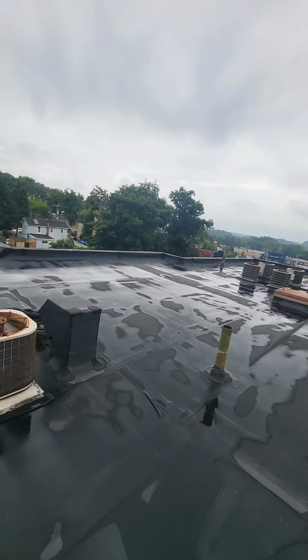But guys, in a nutshell, this was a no AC call. As soon as I got here, nothing was running downstairs. And guys, as soon as I went downstairs, I found the transformer. And by the way, guys, this is the unit that we're working on. And right now, everything is running. But guys, yeah. So as soon as I came downstairs, no AC, I found the transformer burnt up.